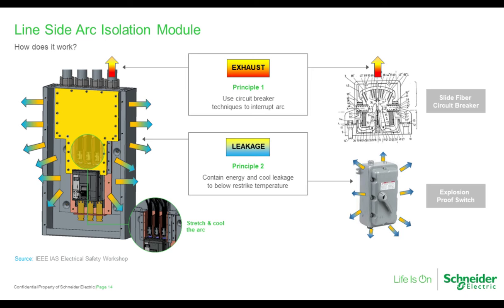To do this, we've added some more features to the ArcBlok shell. Borrowing ideas from our PZ4 arc-resistant switchgear and our explosion-proof switches, we added what we call overlap seals to any leakage paths. We didn't believe that we could build a gas-tight enclosure. We didn't believe that was practically possible to build or maintain. So we built an energy-tight one instead. What this means is that the leakage paths are designed so that any plasma that comes out is squeezed and cooled to below the restrike temperature. This is to avoid an arc being transferred out of the ArcBlok itself and then reigniting somewhere else in the enclosure.